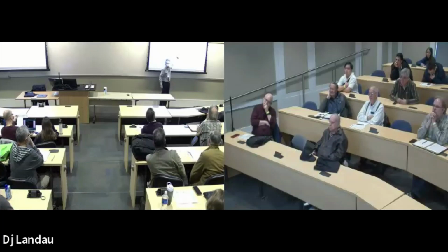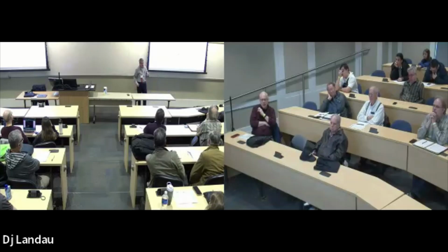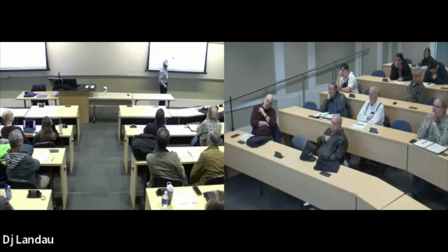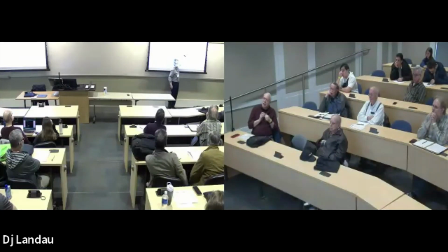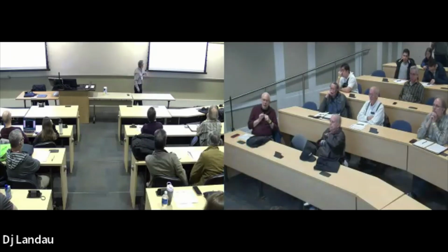This is ultra pure water because we're operating at 1,000 degrees steam temperature and about 2,500 pounds per square inch coming out of the top of the boiler. I mean, this is serious stuff. And so you condense the water and send it back. This condenser is cooled by either a cooling tower or by river water. That doesn't mean it's a nuclear plant. A lot of nuclear plants have those, but that's just a natural draft cooling tower. You have them on any kind of generator.